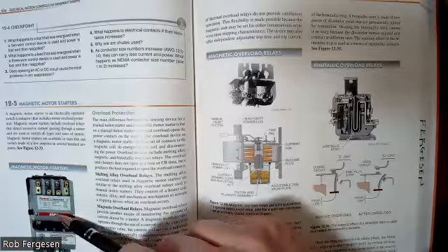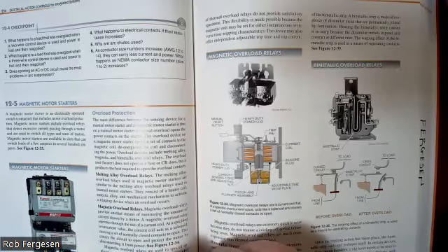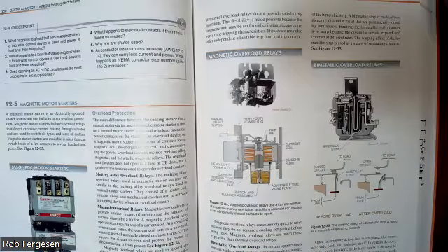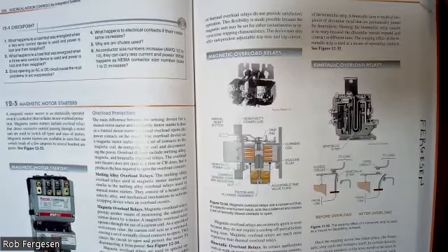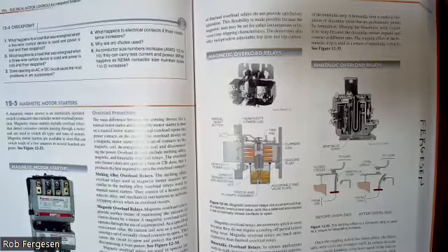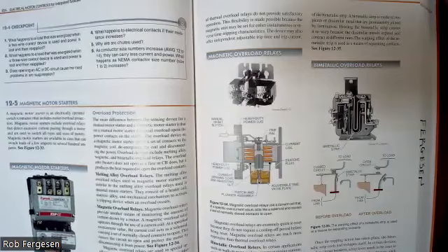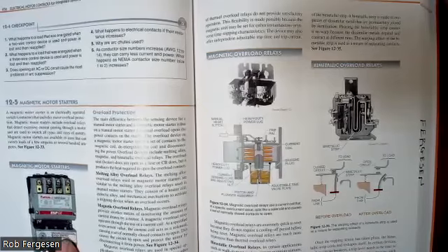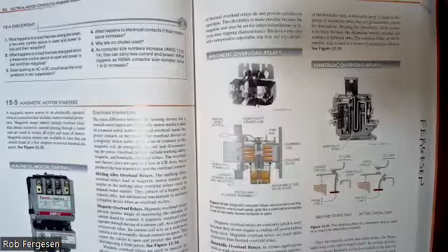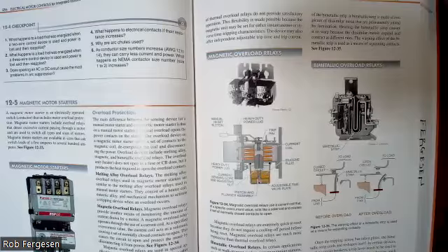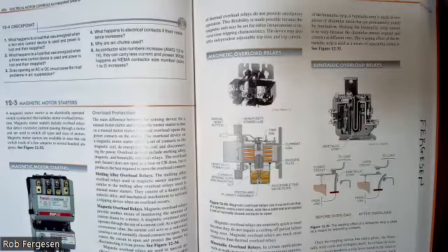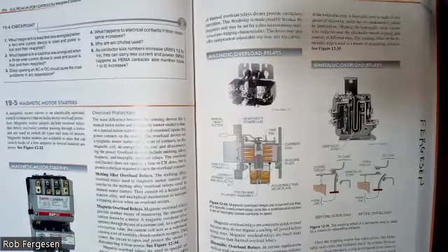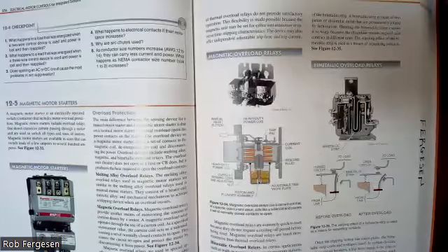You have to follow the directions for setting the current properly. Generally, though, you would set the current to your motor's maximum continuous current right off the nameplate. But obviously, that would depend on the temperature and the environment and conditions, so follow the directions when setting that current. You have to order this in the right range. If you buy one of these that's set up with a range too large or too small, then you're going to have problems running your motor. Actually, too large is not a major issue, except that you won't be getting any current protection. Your motor will cook before the contactor, motor starter, lets it open up.